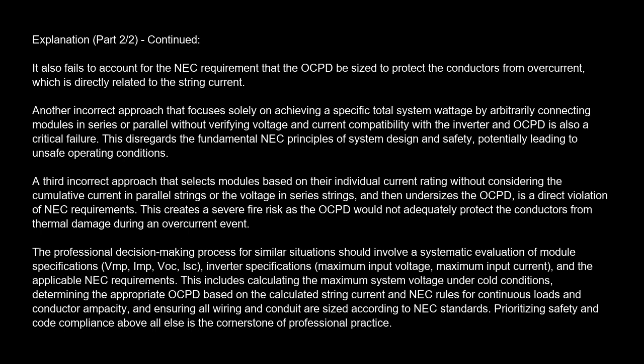A third incorrect approach selects modules based on their individual current rating without considering the cumulative current in parallel strings or the voltage in series strings, and then undersizes the OCPD. This is a direct violation of NEC requirements. It creates a severe fire risk, as the OCPD would not adequately protect the conductors from thermal damage during an overcurrent event.